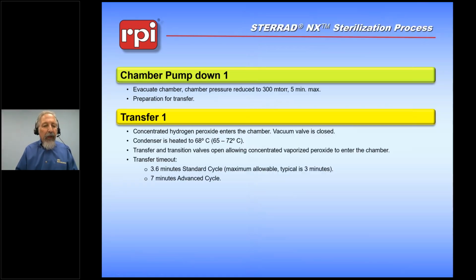Okay, so the transfer time. We keep the valves open for a specific period of time, and we keep the condenser heated to a correct temperature so that none of the peroxide condenses within the transfer system. We look at the hydrogen peroxide through the monitoring system. If it does not show up within 3.6 minutes in the standard cycle, that'll cause a transfer timeout, or 7 minutes within the advanced cycle. The advanced cycles are longer and allow the machine to move the materials at a more leisurely pace.